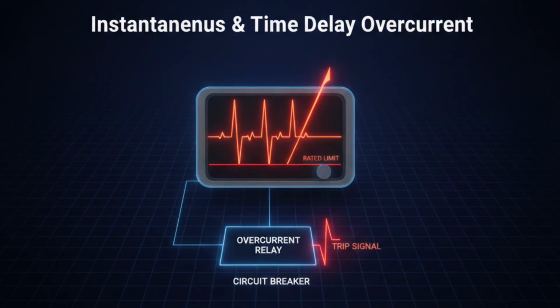Overcurrent protection. Overcurrent means current flowing above the rated limit. This may happen due to overload, mechanical jamming of motors, or partial short circuits. Overcurrent protection relay continuously monitors line current. If the current exceeds preset value, it activates the trip mechanism. There are two types of overcurrent protection. Instantaneous overcurrent, used for very high current conditions. Time delay overcurrent allows temporary high current such as motor starting. This time delay prevents unnecessary tripping during normal starting conditions.